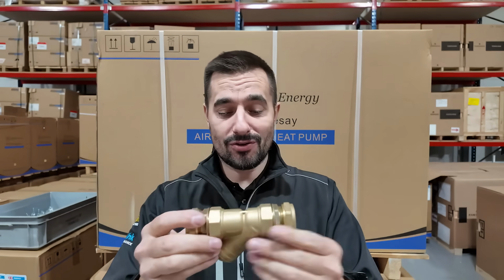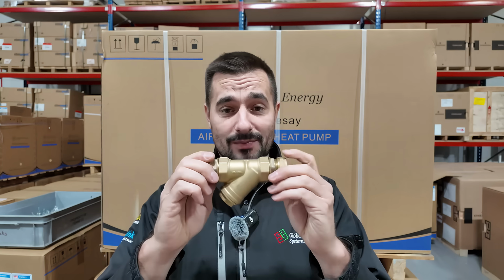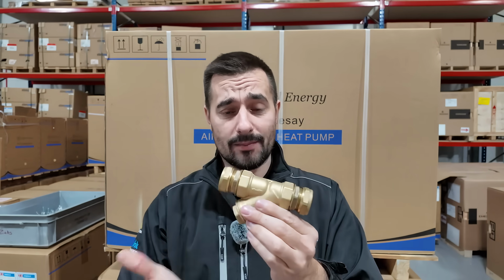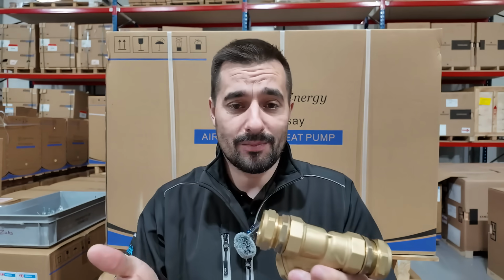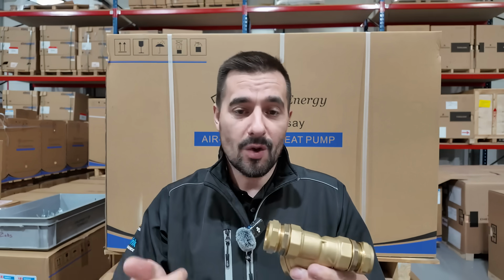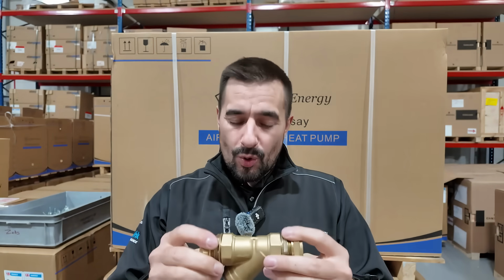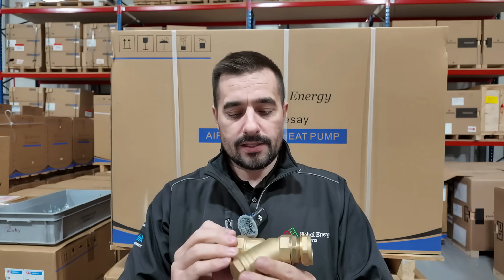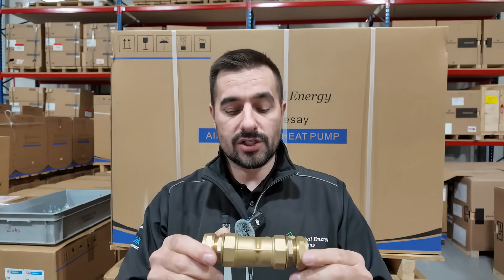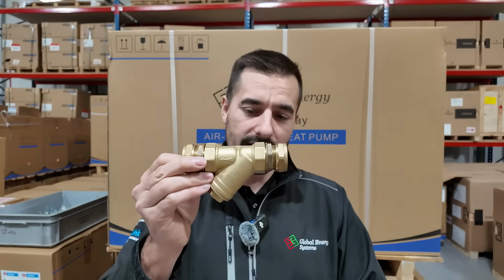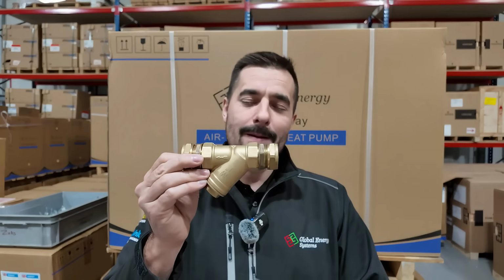So you heat pump installers will know about these things because you'll get nuisance call-outs to clean them out. Now, obviously, system water quality is important. That's like priority number one, whether you use the VDI standard or chemical cleaning. But there's always debris within a system. And no matter how hard you try, there's going to be something. And we've got to protect that condenser. So that was the tool of choice.